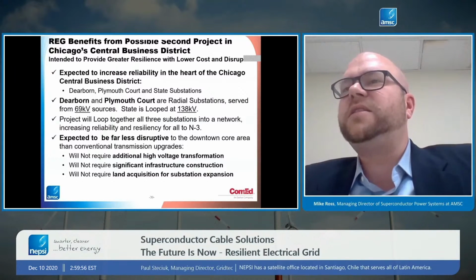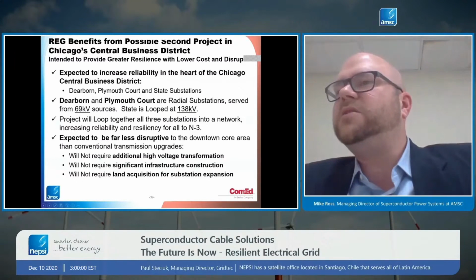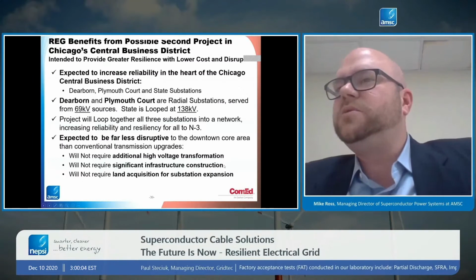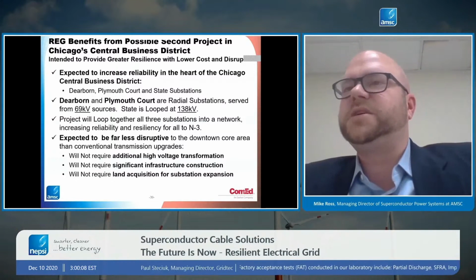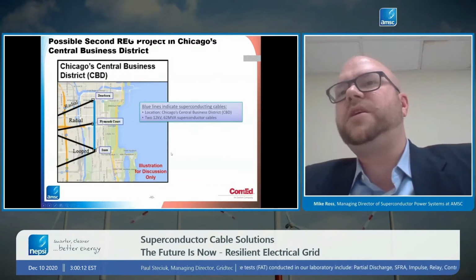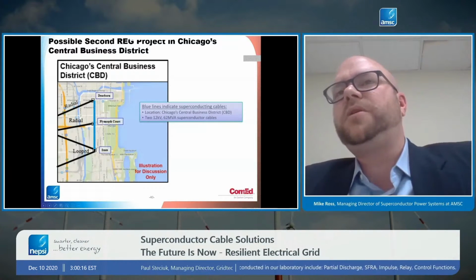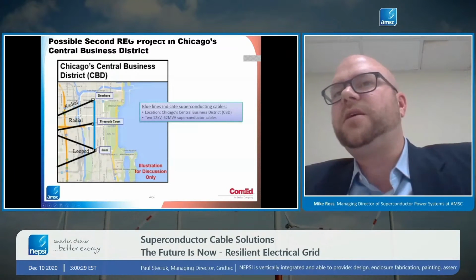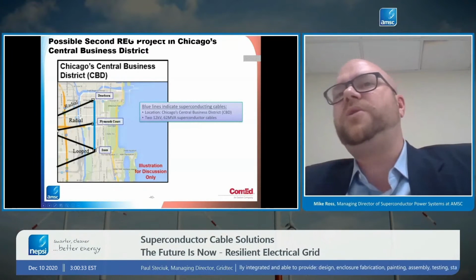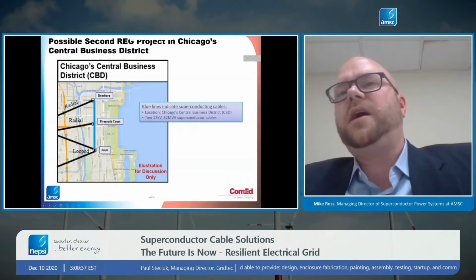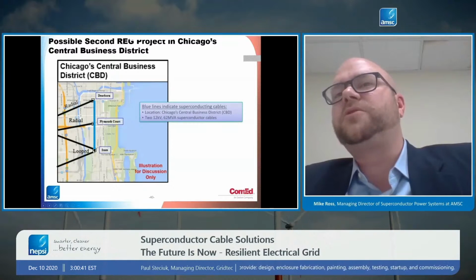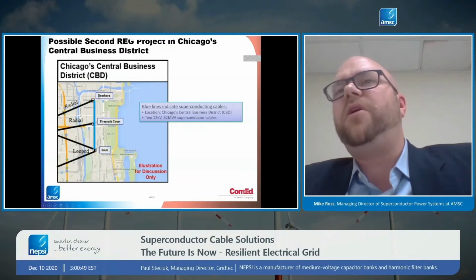Now, what ComEd asked of us is that they have this reliability increase, but without any new high voltage transformers, without any new infrastructure construction, and absolutely no expansion of their existing substations. So here's another look at the project. You have 2 substations, Dearborn and Plymouth Court. They are connected radially to the grid at 69 kV, which means that there is some redundancy. So there's 4 circuits of 69 kV here, but there's an opportunity for an outage if you have an outage in this circuit. State, however, is a much more reliable substation. It's got multiple sources to it. So by interconnecting these 3 substations together with a superconductor cable, we can increase the reliability of all of these substations in the event you lost the traditional service.